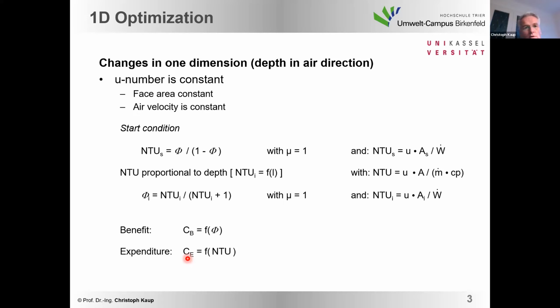What we did at the first point was to think about how to optimize the heat recovery system. One point is very clear: the benefit of the heat recovery system is linked to its efficiency. Very easy: a heat recovery system with 40% will have only half of the benefit of a heat recovery system with 80%. But unfortunately, the expenditure or the effort is linked to the NTU, the number of transfer units, the size of the heat recovery system itself. And the 1D optimization is based on a constant face area, so a constant air speed. So we are only changing the depth of the heat exchanger to find the optimum.